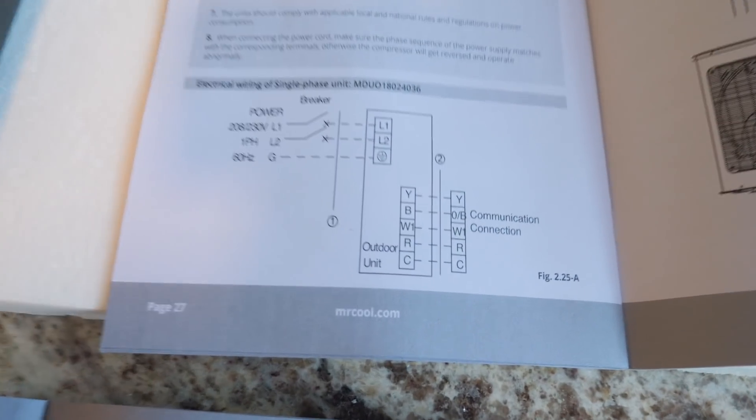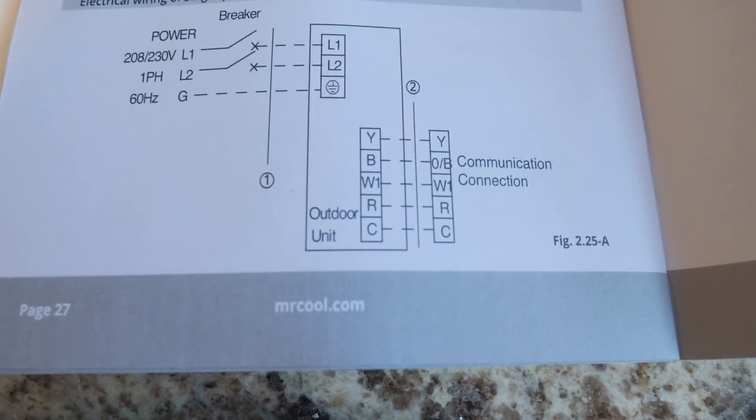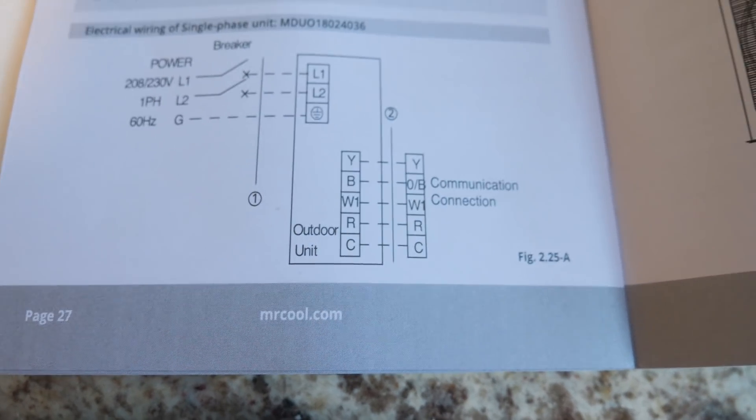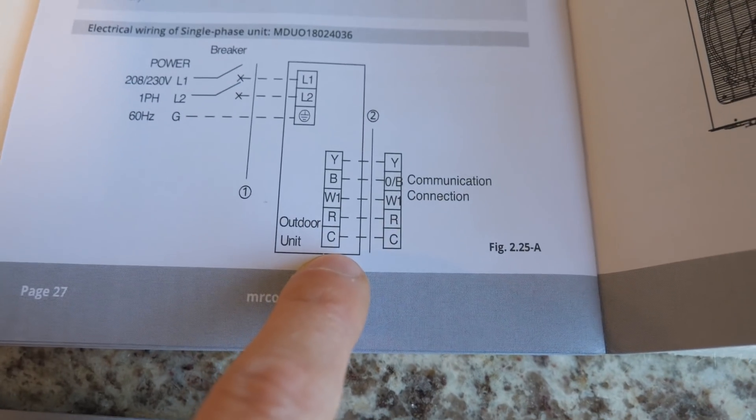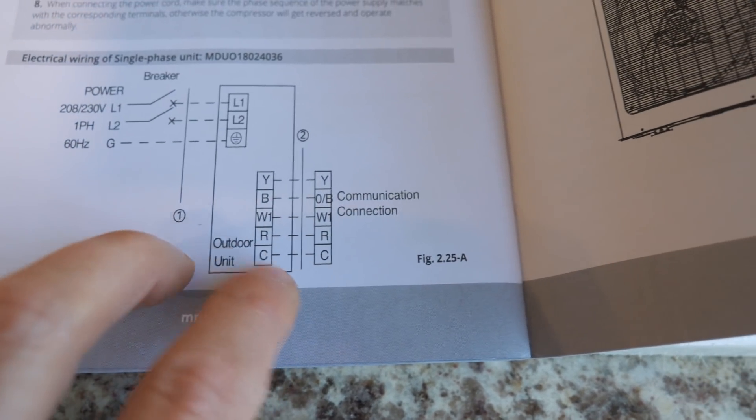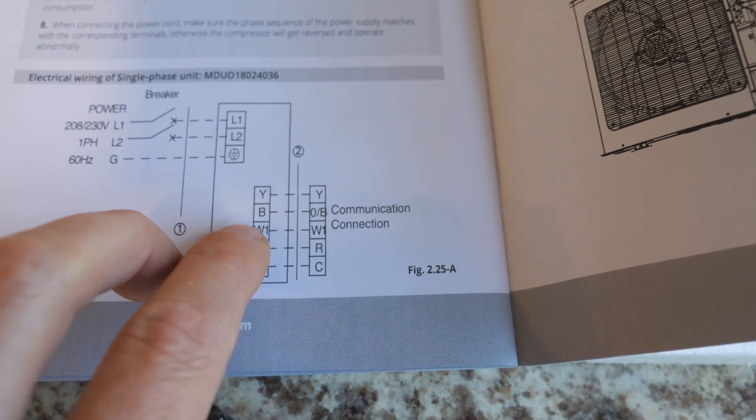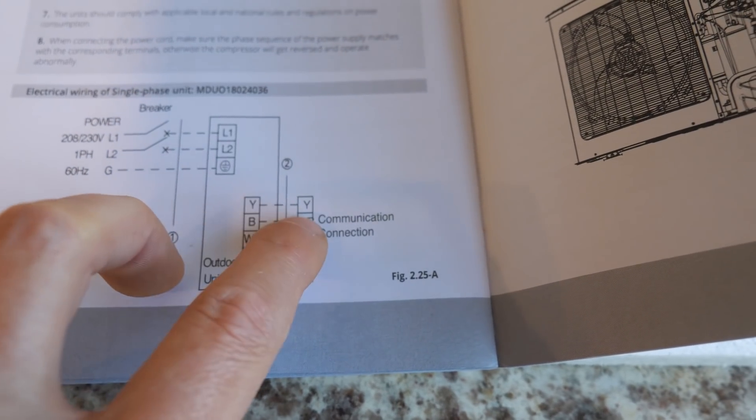So you got to make sure you got the right colored wire to the right terminal, depending on the system you're using. This is the outdoor unit of the system we're using. And the indoor connection to the outdoor unit. So regardless of wire color, C goes to C, R goes to R, W1, B goes to OB, and Y to Y.